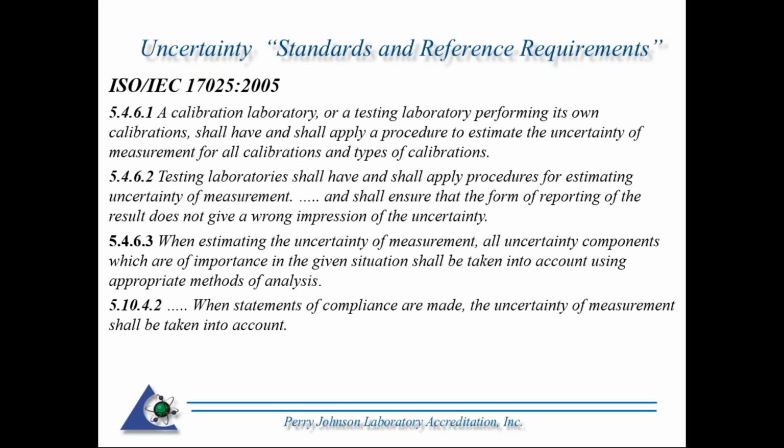A calibration laboratory, or a testing laboratory performing its own calibrations, shall have and apply a procedure to estimate the uncertainty of measurement for all calibrations and types of calibrations. One thing you're going to see different, with the entire revision of the standard, is that you still have to be able to determine uncertainty, but the requirement of having an actual procedure is slimmed down quite a bit in the new standard, primarily because we've gone from paper to electronic. So oftentimes uncertainty is a methodology of entering data into the computer, looking up data, things like that.